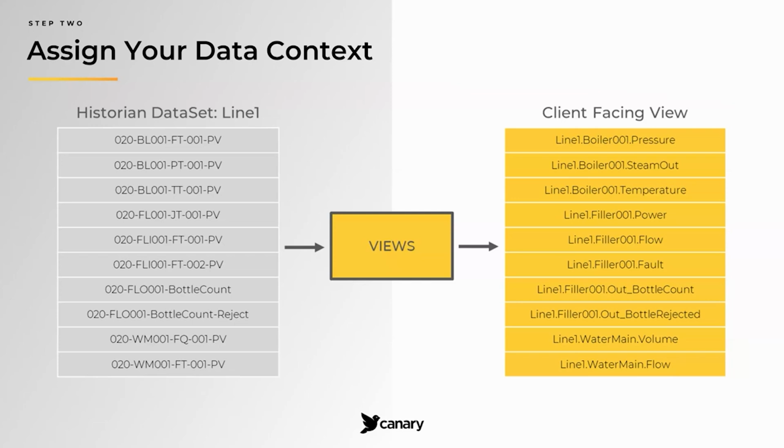The View service allows the system administrator to add context to the Canary Historian archive. It allows you to reshape and alias historized tag formats without changing the tag in the archive. It also allows for the creation of asset model buildouts with parent-child relationships. And historian tags can be associated to multiple asset models and do not require additional tag licenses.